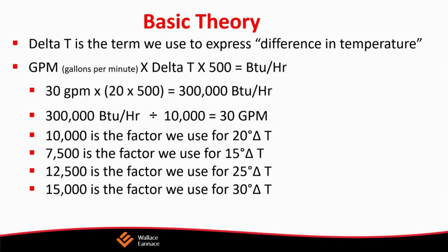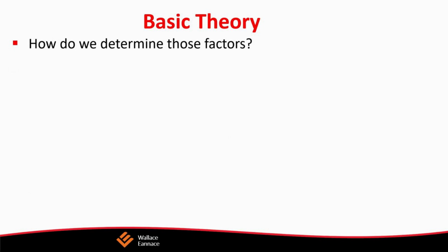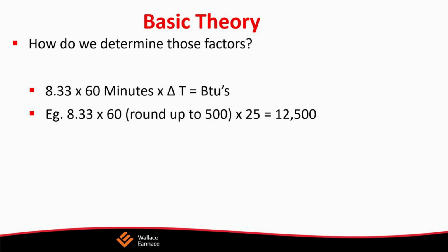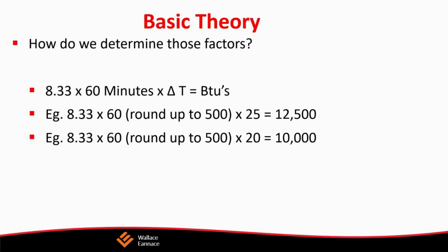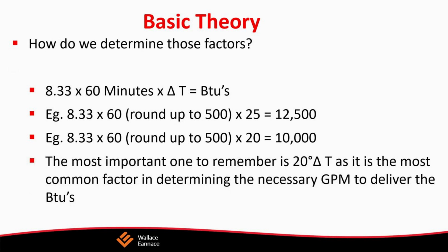So what is delta T? Delta T is a term we use to express the difference in temperature. For instance, if we have water entering a radiator at, say, 180 degrees, and it leaves the radiator at 175 degrees, we've had a 5-degree delta T. Gallons per minute times the delta T times 500 gives us the BTUs per hour. So 30 gallons a minute times 20 times 500 equals 300,000 BTUs. If we had a 20-degree delta T in a heating system, and our flow was 30 gallons a minute, we would deliver 300,000 BTUs.